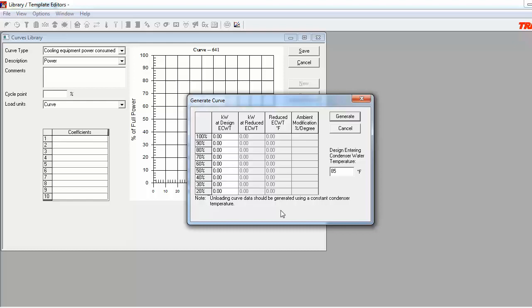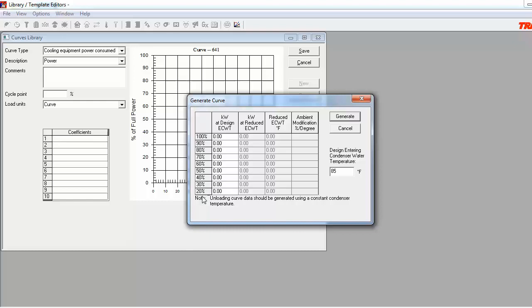Note that this input window is broken up into several columns with an additional input field on the right-hand side. As stated before, the power-consume curve needs to be built based on compressor performance data generated by unloading the compressor on the evaporator side of the equipment, while maintaining a constant design condenser entering temperature. The condenser temperature will be based on either water or air-dry bulb, depending on the equipment being modeled. The text on the input box on the right-hand side will not update to reflect air-dry bulb temperatures for air-cooled equipment, but as you will see later, we will be able to delineate this when creating the ambient modification curve. The Load column on the left-hand side of the window is broken up into 10% increments. You will need to populate the second column with the KW draw for the compressor at each load point. The two other columns are not required at this point, nor are they accessible. Now, where can this data be acquired?